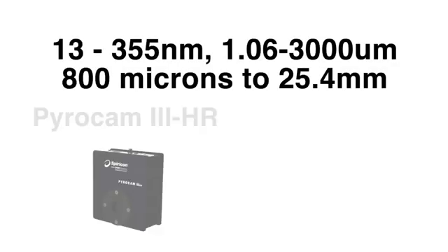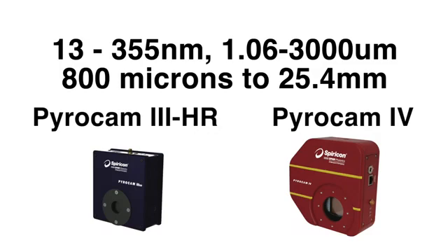The PyroCam 3HR and PyroCam 4 measure UV and infrared lasers out into the terahertz wavelengths, with beam sizes of 800 microns to 25.4 millimeters.